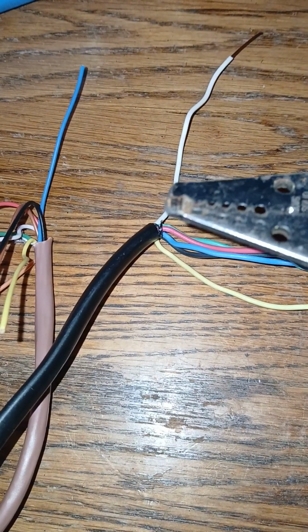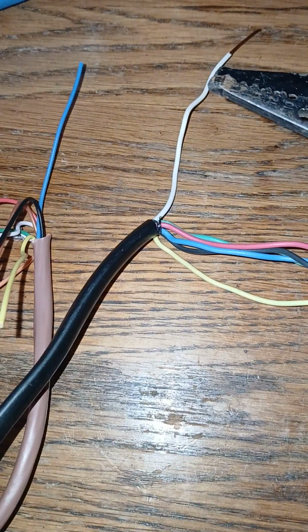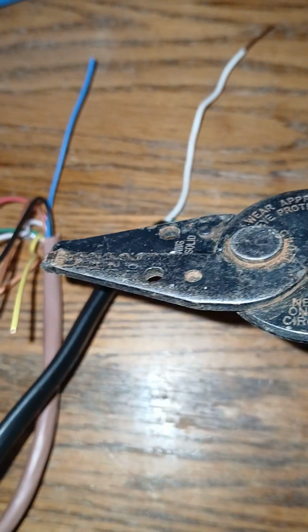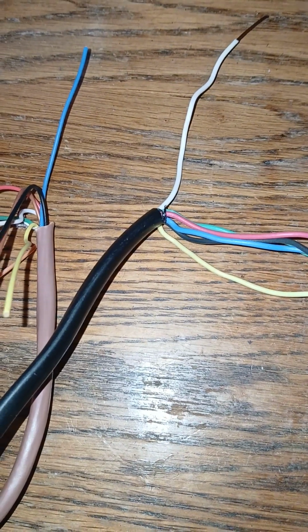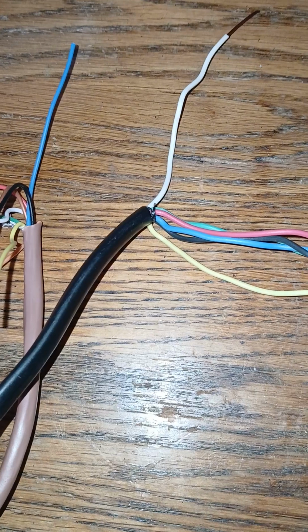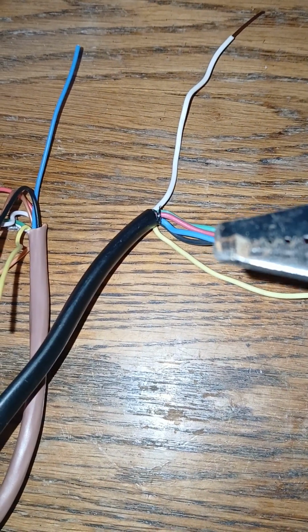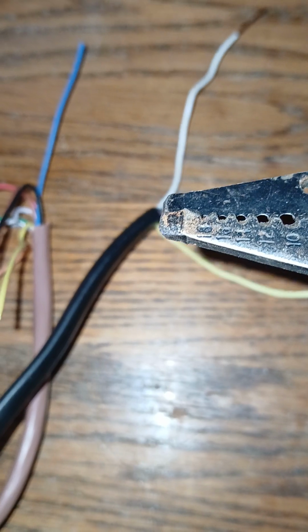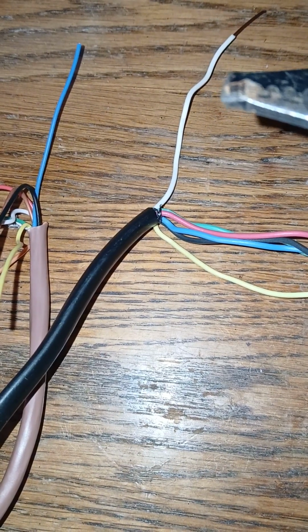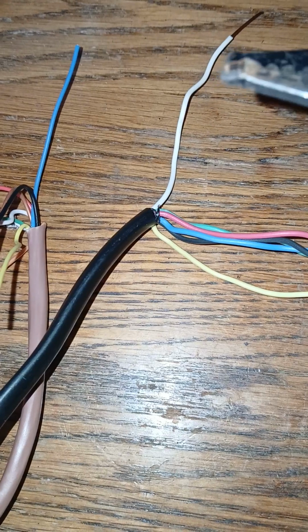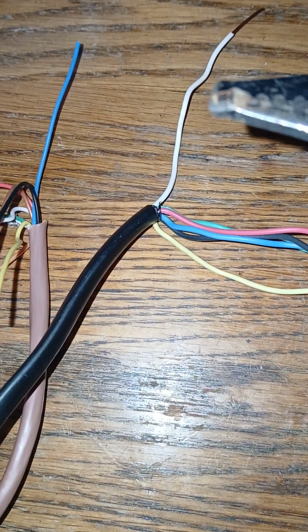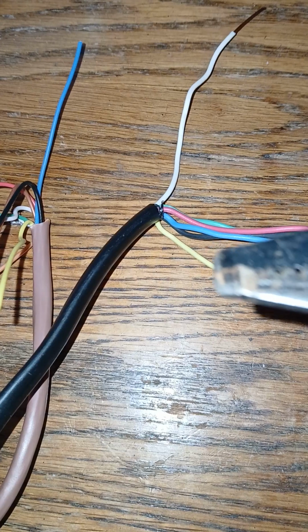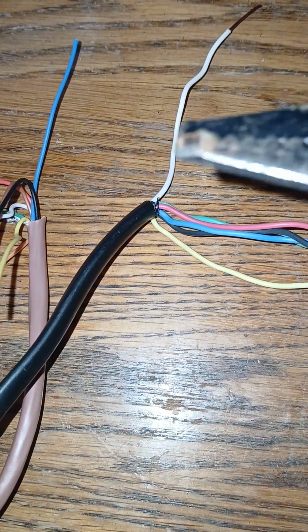Again, for the lawn sprinkler system, the common wire is the white wire. For the HVAC thermostat wiring, the common wire is the blue wire. Now keep in mind, if one of these other wires gets broken and there's an extra wire, you may use that extra wire, so you'll have to look in the box or follow the wiring to find out, because they may have used a different color wire for the common simply because the original common wire was broken. The same thing can happen in the HVAC industry.